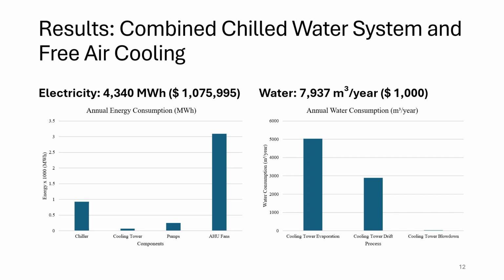This result shows a scenario where combined chilled water system and free air cooling are used for cooling the data center. The electricity demand reduces to 4,340 megawatt hours a year, which reduces the electricity bill to just over $1 million. Most of the energy is used by the air handler unit fans, followed by the chiller, then the pumps and the cooling tower. The system also uses significantly less water, just below 8,000 cubic meters a year, costing $1,000.